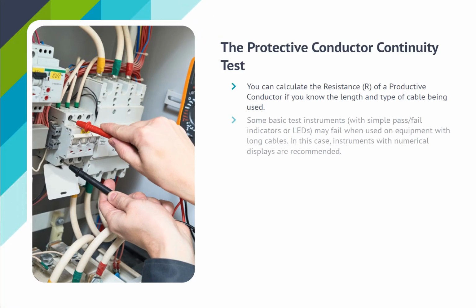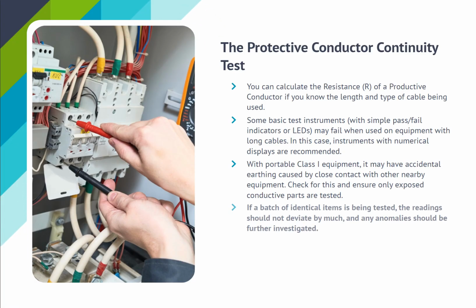You can calculate the resistance, R, of a protective conductor if you know the length and type of cable being used. Some basic test instruments, with simple pass or fail indicators or LEDs, may fail when used on equipment with long cables. In this case, instruments with numerical displays are recommended. Portable Class I equipment may have accidental earthing caused by close contact with other nearby equipment. Check for this and ensure only exposed conductive parts are tested. If a batch of identical items is being tested, the readings should not deviate by much, and any anomalies should be further investigated.